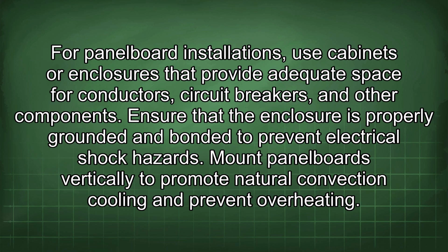For panel board installations, use cabinets or enclosures that provide adequate space for conductors, circuit breakers, and other components. Ensure that the enclosure is properly grounded and bonded to prevent electrical shock hazards. Mount panel boards vertically to promote natural convection cooling and prevent overheating.